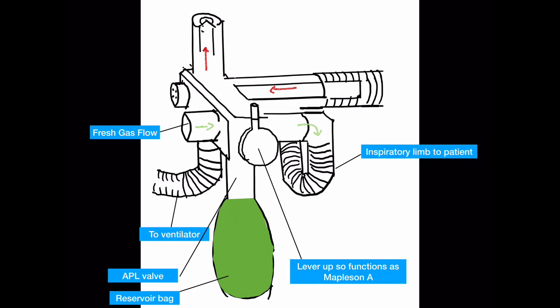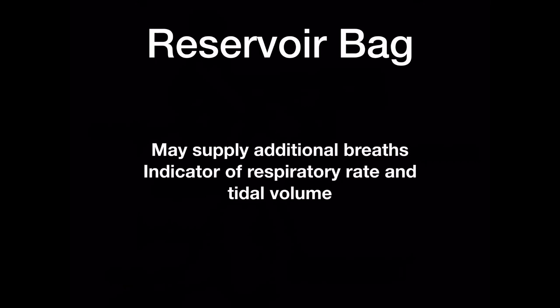Schematic and mechanism of action. With the lever in the up position, the reservoir bag and APL valve are connected in the same configuration as a Mapleson A circuit and the patient is able to breathe spontaneously. Fresh gas passes through the fresh gas port and is delivered to the patient via the inspiratory limb. During its passage, some of the fresh gas flow will fill the reservoir bag, which can be used by the anaesthetist to supply additional breaths and also acts as a crude indicator of the patient's respiratory rate and tidal volume.